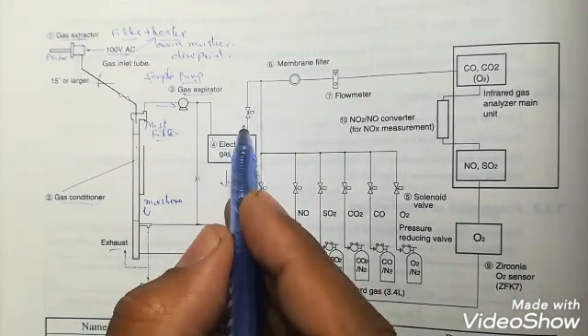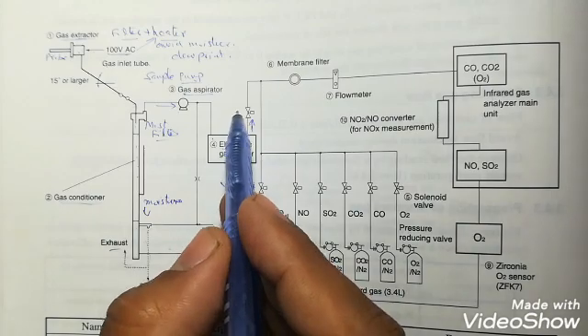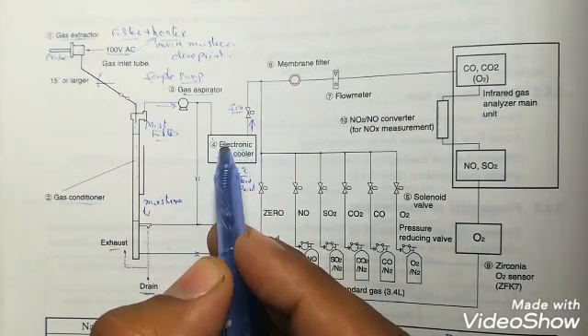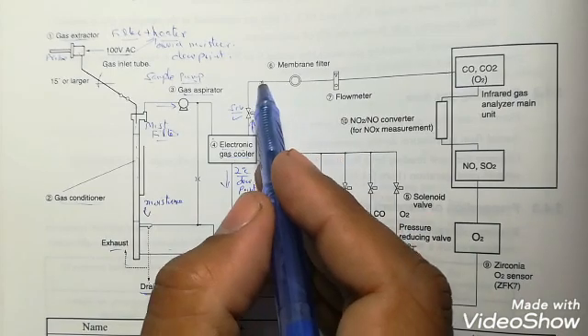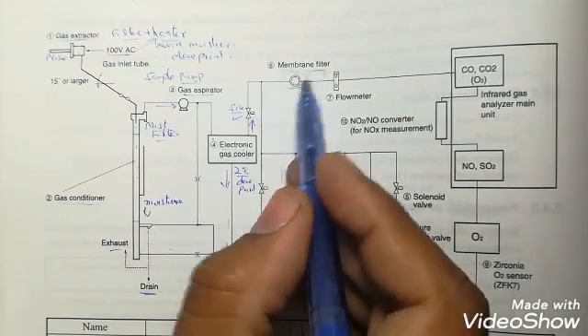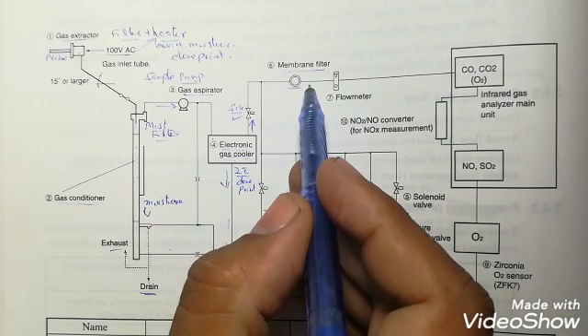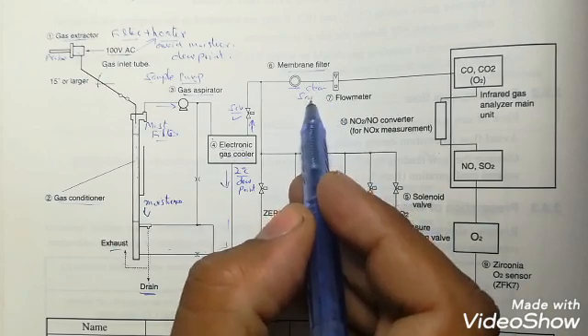This cooler cools the sampling gas up to 2 degrees centigrade. This is the dew point. Any moisture inside the sample changes into water and then drains out. A clean sample outside of the gas cooler is given to this SOV.